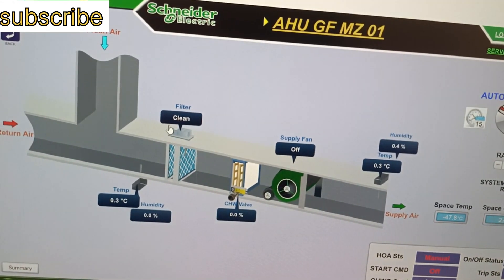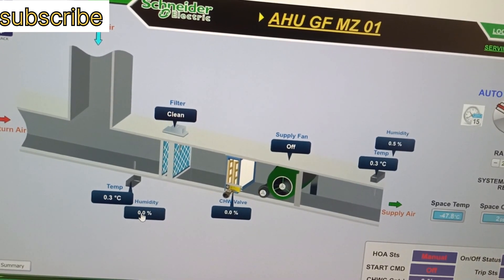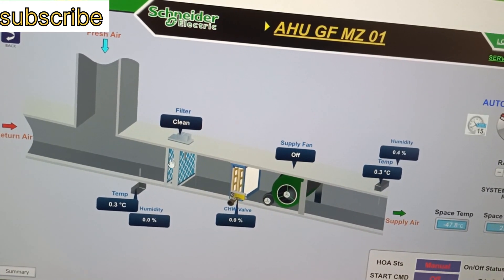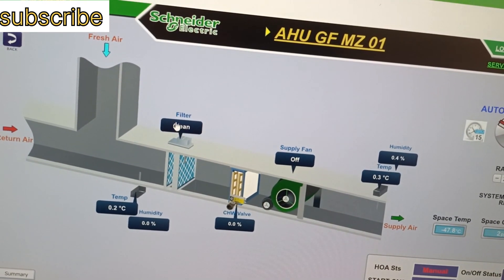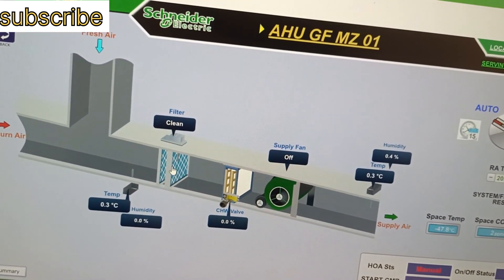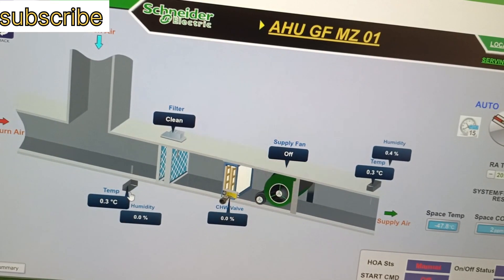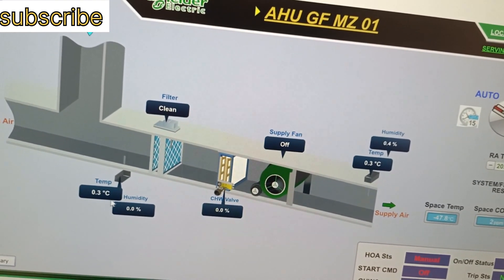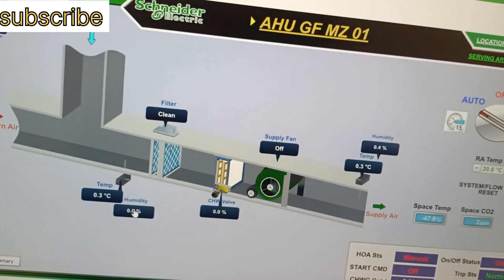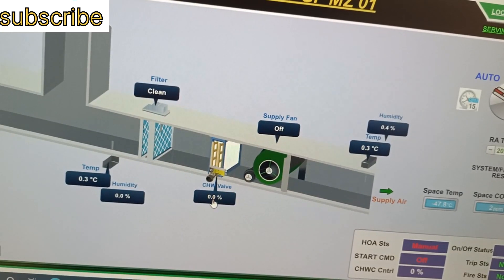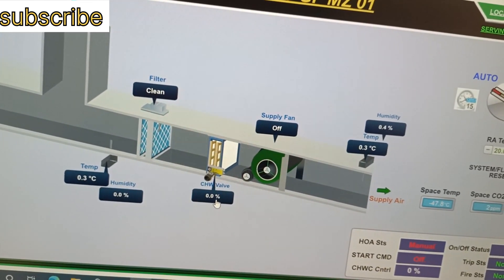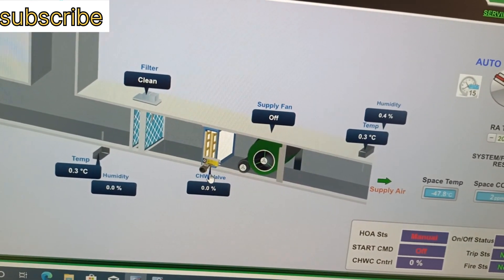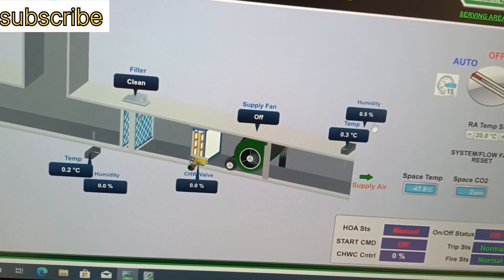Here we have a temperature and humidity sensor. The fresh air duct and return air duct are shown, with a filter in between — it is showing clean. The temperature and humidity sensor is showing 0.3 degrees Celsius, which indicates a problem. The chilled water valve is also showing 0.0 percent, and the supply fan is off — we are not getting any status for these either.